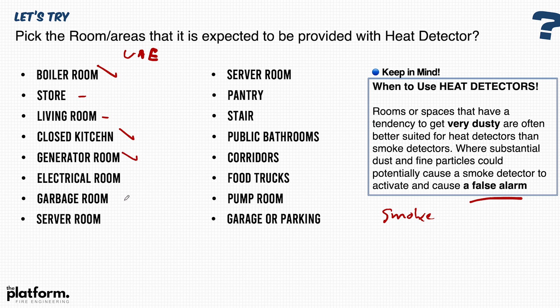Generator rooms also have a chance of smoke generated from the generator and exhaust pipe, which can cause false alarms. Garbage rooms sometimes require a heat detector. Pantry and stairs are normal areas. Server rooms are normal. Public bathrooms require a heat detector to avoid false alarms caused by condensation, steam, or other moisture-related reasons. Corridors are normal usage so we install smoke detectors. Food trucks require a heat detector since there is cooking inside.